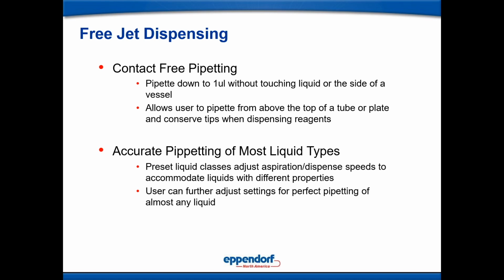Also, you might say, well, how is it going to pipette glycerol and other liquids that are thick or have a high vapor pressure and so on? Well, we have preset liquid classes in our machine. You simply choose the appropriate liquid class. Use the ethanol settings for things with high vapor pressure. Use the glycerol settings for viscous liquids up to say 20% glycerol. And the machine changes the way it pipettes. It will allow more time for liquid to get in, and more time for liquid to settle at the bottom of the tip before blowout if it's a viscous solution.